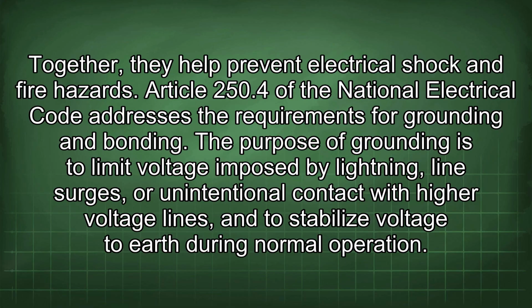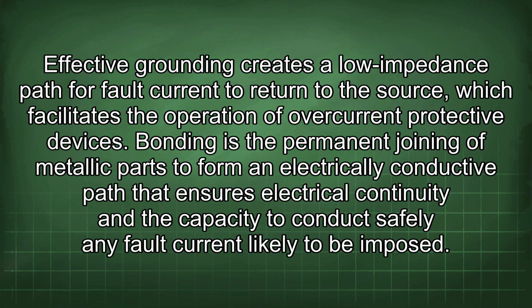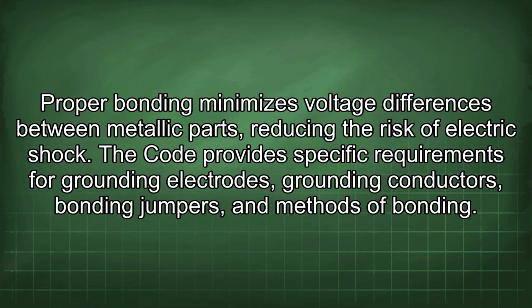The purpose of grounding is to limit voltage imposed by lightning, line surges, or unintentional contact with higher voltage lines, and to stabilize voltage to earth during normal operation. Effective grounding creates a low-impedance path for fault current to return to the source, which facilitates the operation of overcurrent protective devices. Bonding is the permanent joining of metallic parts to form an electrically conductive path that ensures electrical continuity and the capacity to conduct safely any fault current likely to be imposed. Proper bonding minimizes voltage differences between metallic parts, reducing the risk of electric shock.